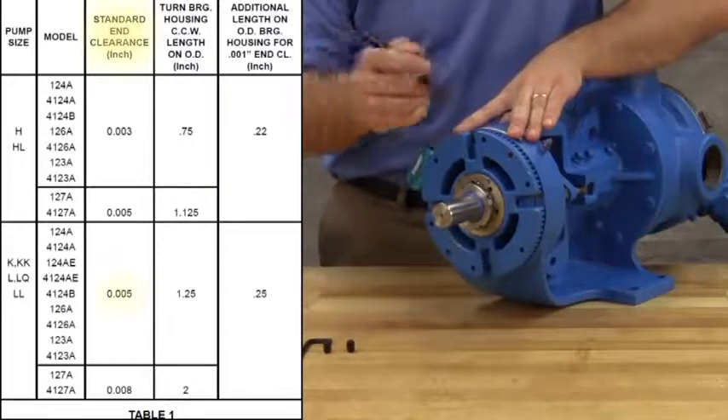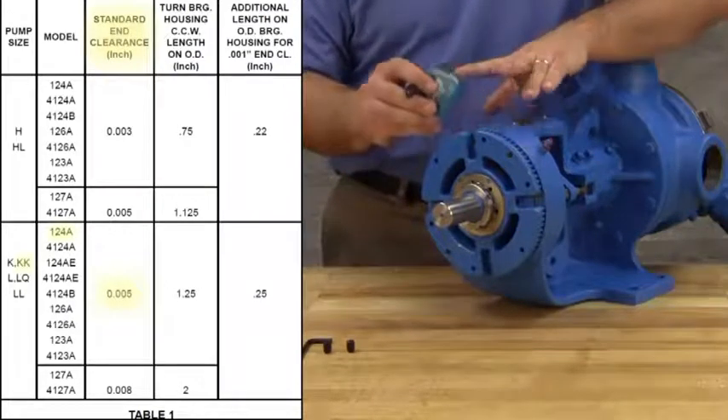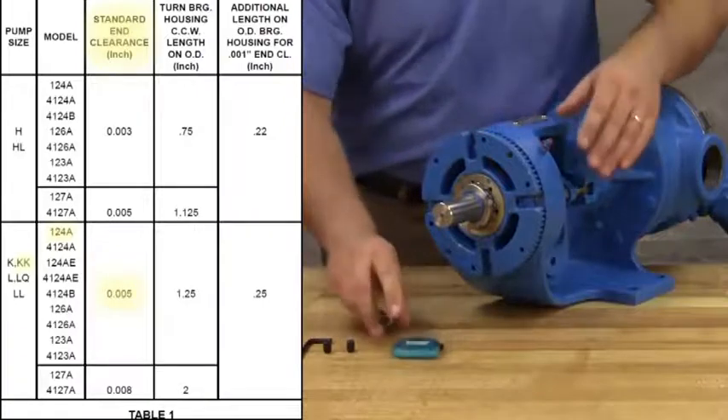Here we require five thousandths of an inch end clearance for a model KK124A pump, so the mark is made 1.25 inches away.